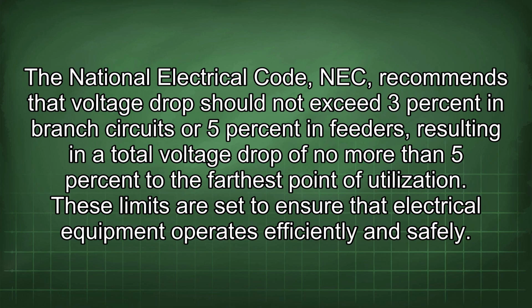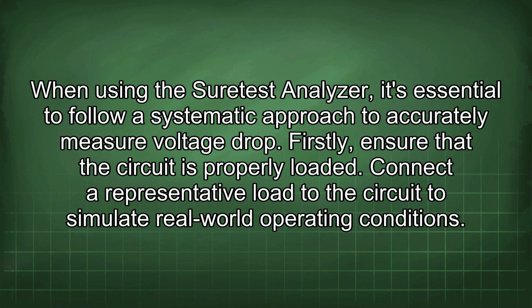The National Electrical Code (NEC) recommends that voltage drop should not exceed 3% in branch circuits or 5% in feeders, resulting in a total voltage drop of no more than 5% to the farthest point of utilization. These limits are set to ensure that electrical equipment operates efficiently and safely. When using the Suretest Analyzer, it's essential to follow a systematic approach to accurately measure voltage drop.